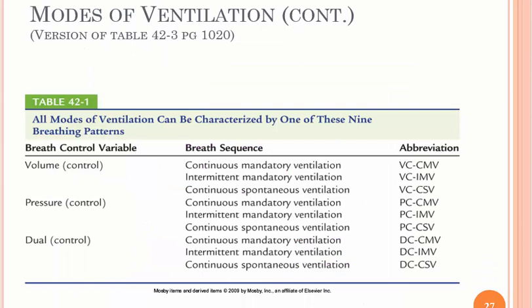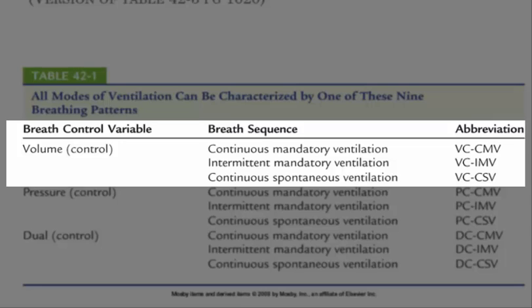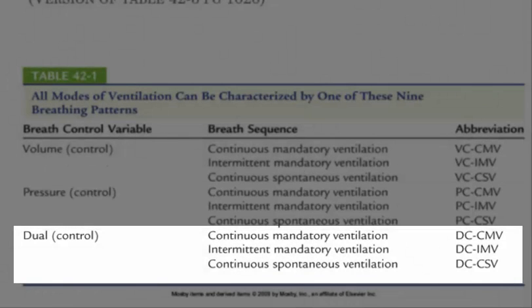A table describes the modes: in volume control you can have continuous mandatory ventilation or intermittent mandatory ventilation, with abbreviations beginning with VC for volume control. In pressure control the same options exist, abbreviated PC-CMV for pressure control. And for dual control where one variable becomes a target, the abbreviation is DC-CMV.